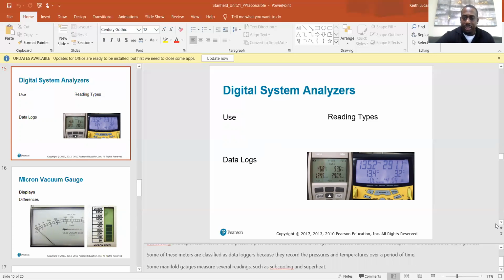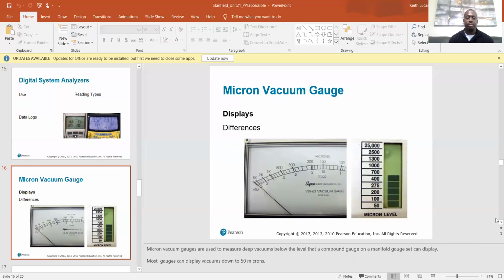So get you some digital gauges. You can read your superheat, subcool, your saturation temperatures for every single refrigerant, everything you need in one. Your micron gauge, all of it. So, moving into micron gauges. Micron vacuum gauges are used to measure deep vacuums below the level that a compound gauge on a manifold gauge set can display.